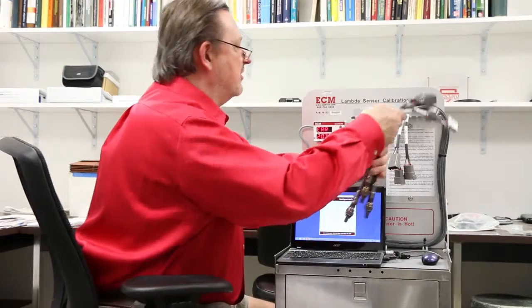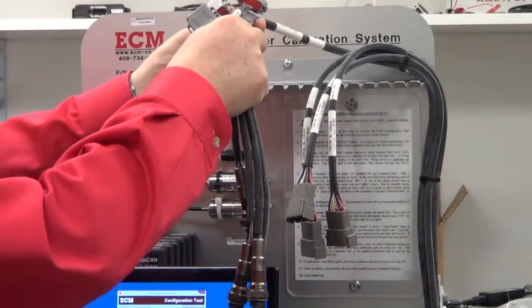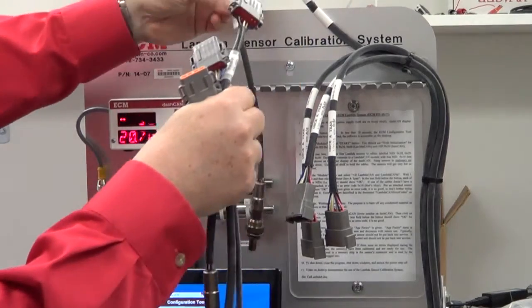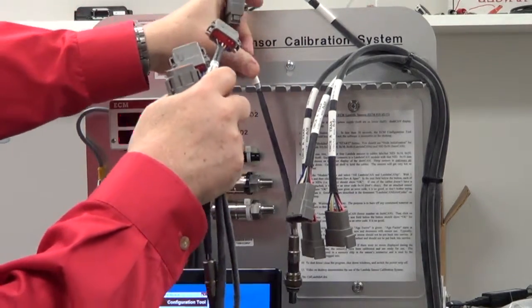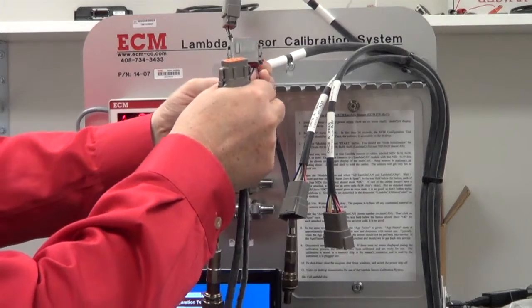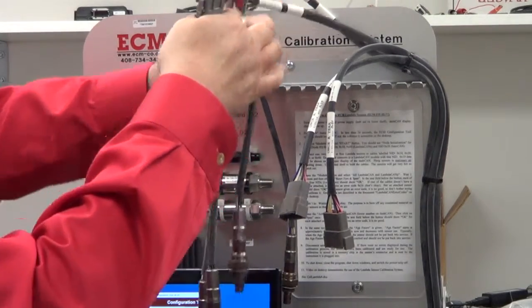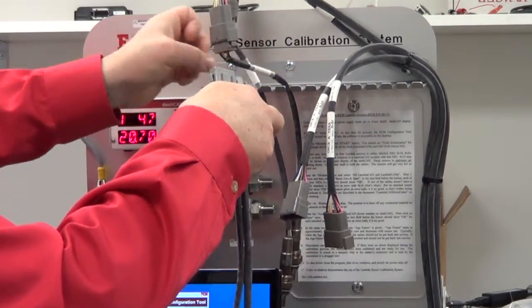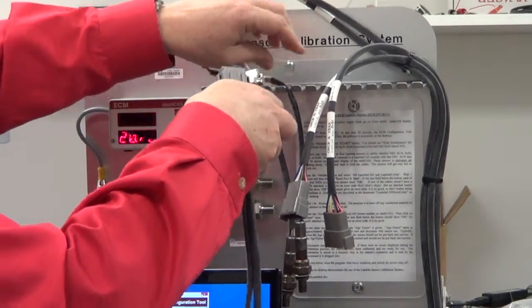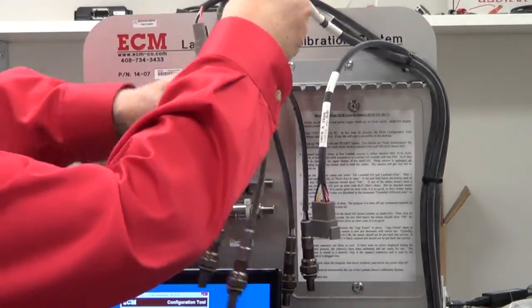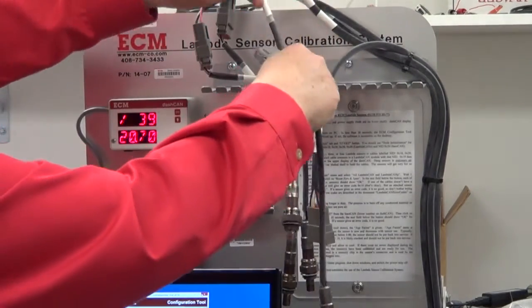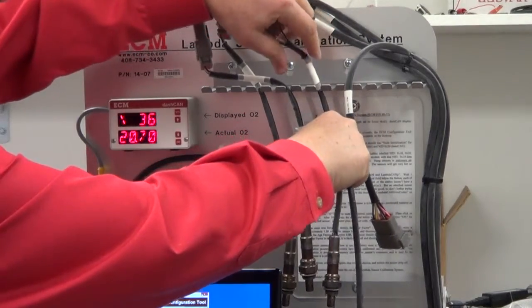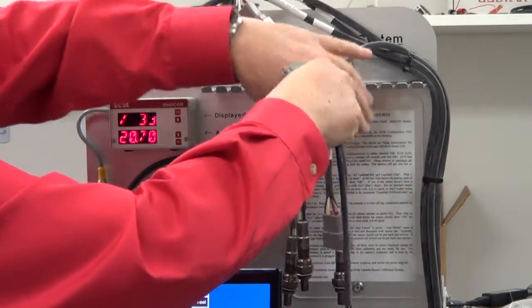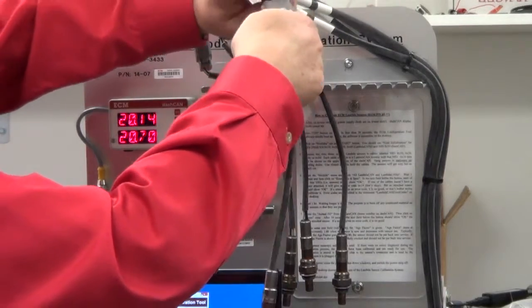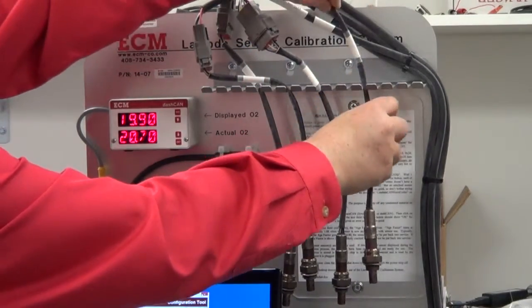So I'm going to attach, I have 4 sensors here, and I'm going to attach them. Click. And you hang them here, they're going to get hot. Not immediately, but give it a couple minutes to get hot. So I like to put them here, hang them so they're not on the table or sitting against something plastic. Depending on which sensor you're calibrating, different types will have different cable lengths. And so with this system, you can handle all of them. There you go.